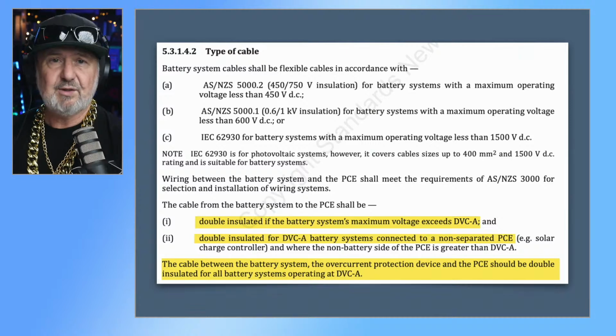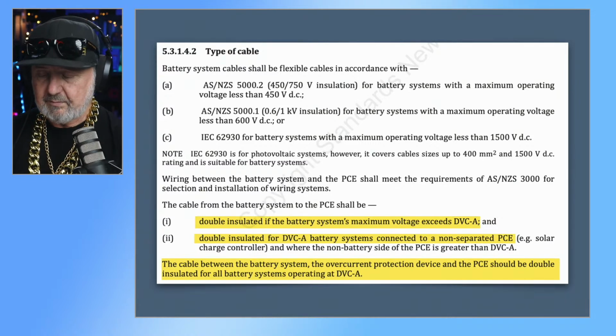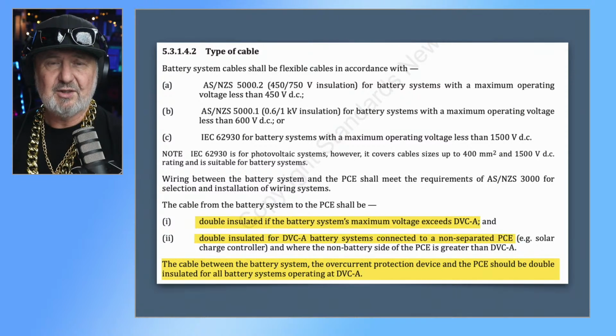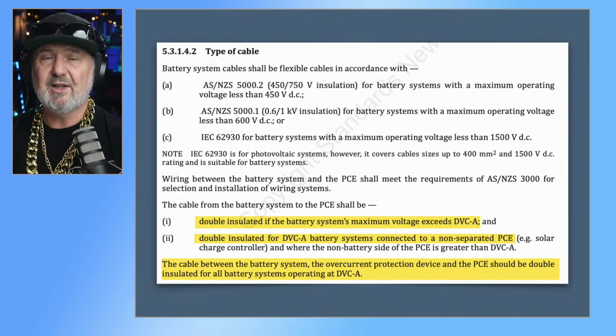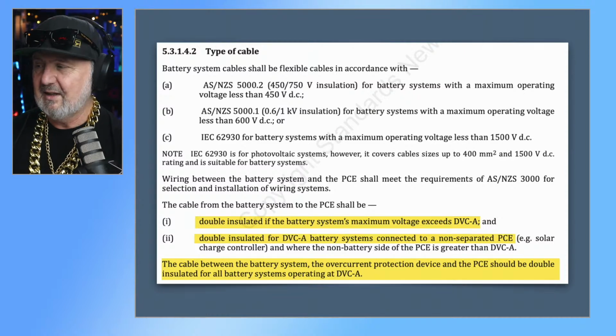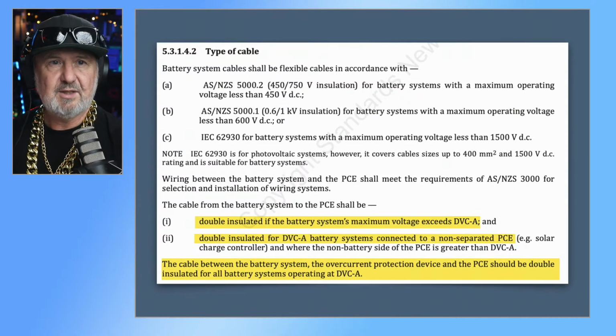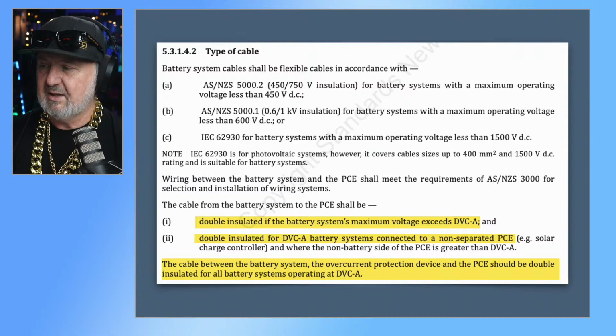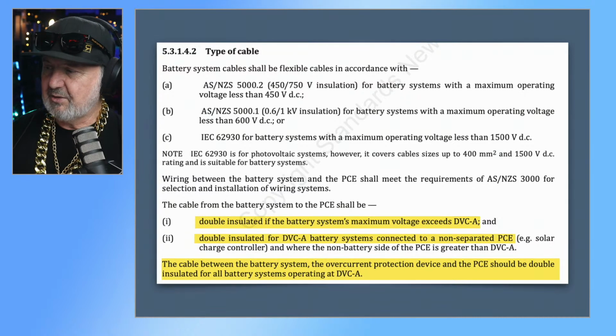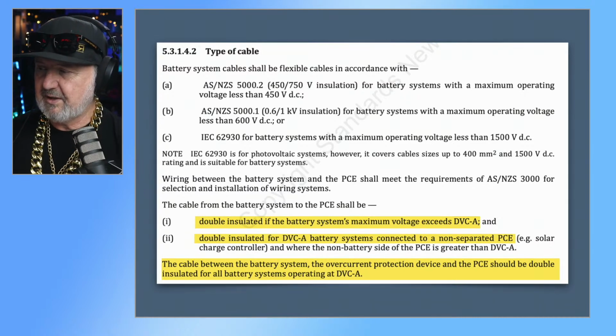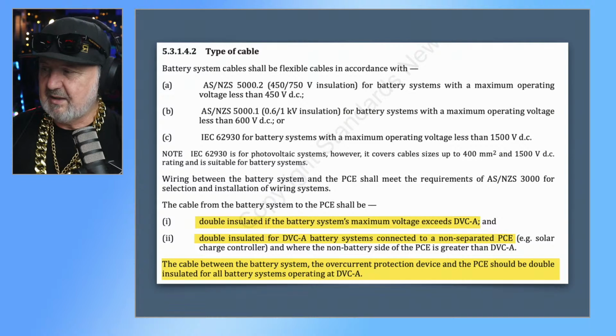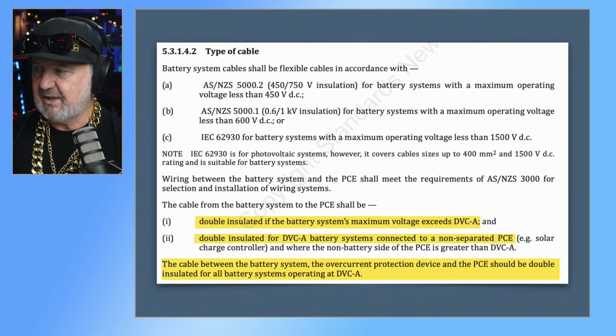I know that the Victron RS450 does, the AERL MPPTs have galvanic isolation, but it's a pretty rare one. Oh, and Schneider as well. I can only think of 3. Schneider 600/80 unit. So it's pretty rare. So effectively, you're going to have double insulated cables when the PCE side is above DVC-A.